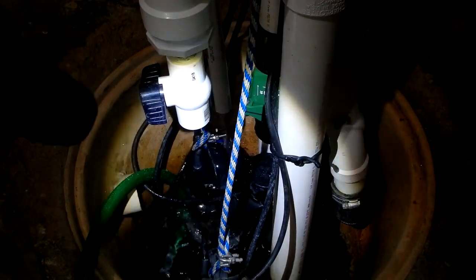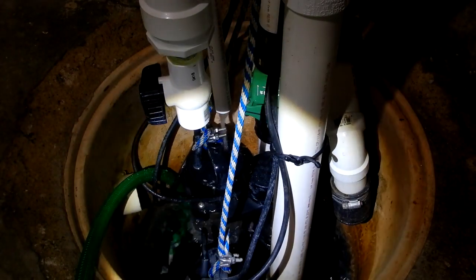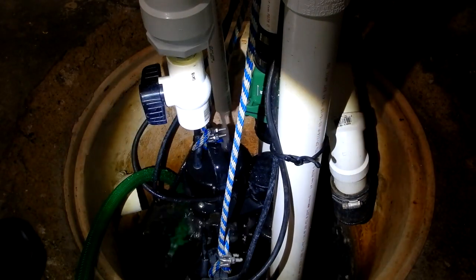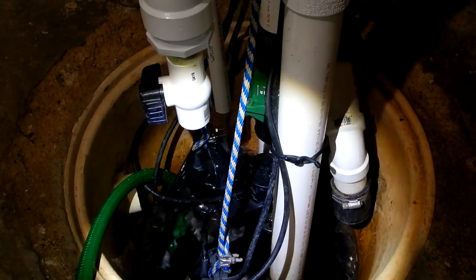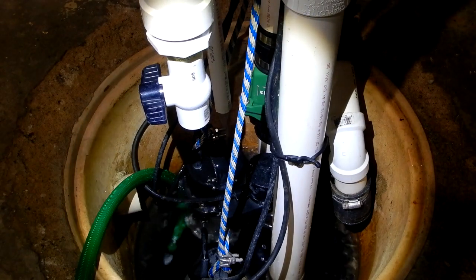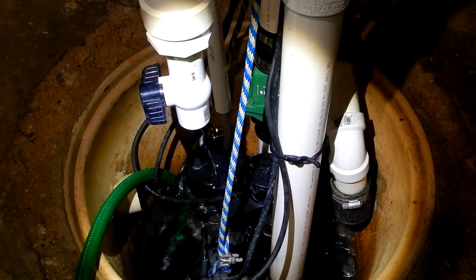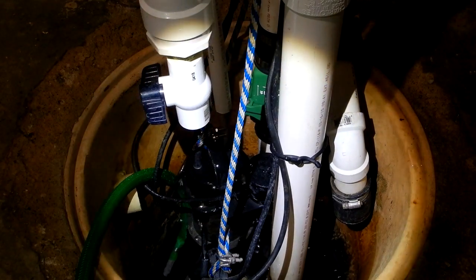Once it's done its initial hesitation, there is no issue with that higher-standing pipe. This simulates the front pump going out and the secondary pump taking over. As you can see, absolutely no issue. Without doing what I've done here, that pump would just continue to run and not pump. Now I'm going to describe what's going on here.